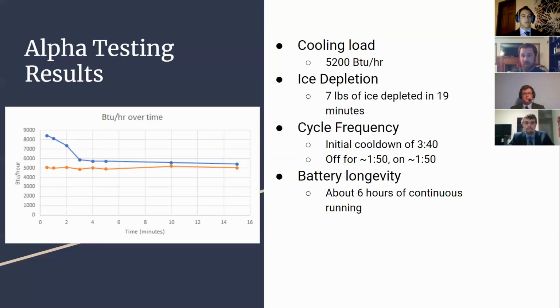So this graph really makes sense in the fact that a room has cold and hot pockets of air, and as the air is stirred up and mixed, you'll have higher and lower temperature, and this reflects in it going up and down in the orange with the air. And as far as the water, once everything starts up, you have to cool down the system, and this is why you have such a high BTU per hour. There's a high change in temperature, and once everything's cooled down, then it levels out, and it shows this in the graph where the blue kind of levels out.